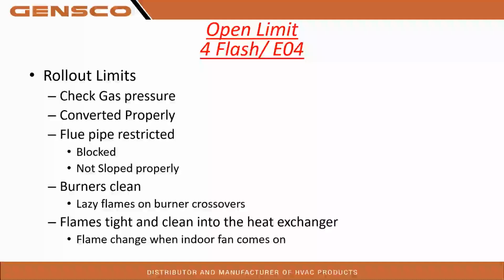So we get the question a lot when it comes to gas furnaces from homeowners and even technicians. And I'm going to raise the question. You have an inducer motor putting a negative pressure on the heat exchanger. So you have a negative pressure, you have it monitored with rollouts, and you have it monitored with pressure switches. So we get the call all the time where, oh, the furnace is putting carbon monoxide into the space. That would be very hard to do, knowing that the heat exchanger is in the negative pressure. So it's being pulled through the heat exchanger and out the flue pipe.